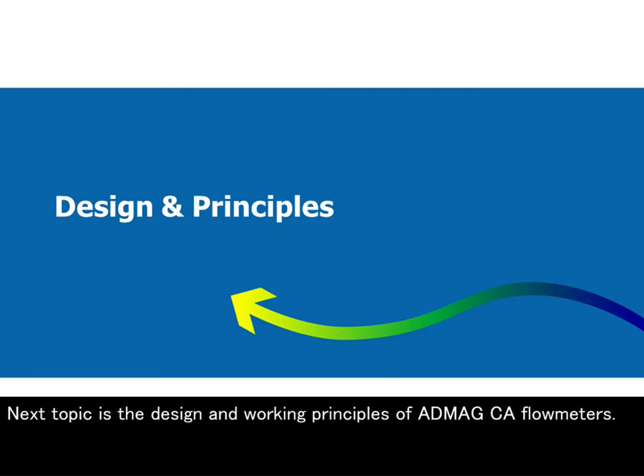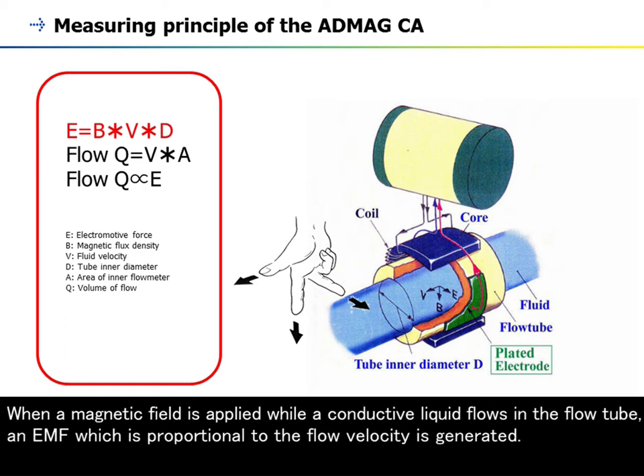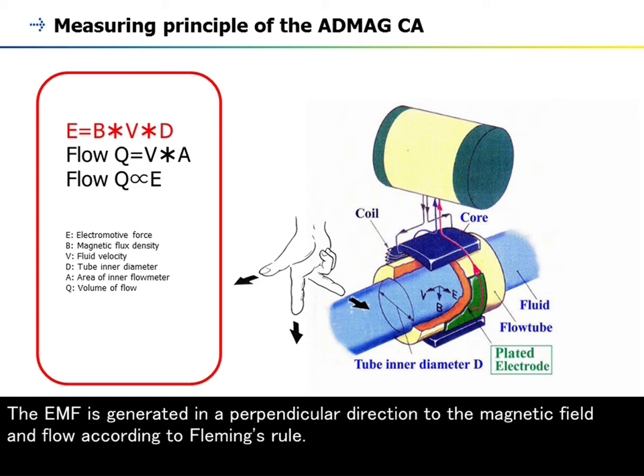The next topic is the design and working principles of ADMAG CA flow meters. The measuring principle of the ADMAG CA is based on Faraday's law of electromagnetic induction. When a magnetic field is applied while a conductive liquid flows in the flow tube, an EMF which is proportional to the flow velocity is generated. The EMF is generated in a perpendicular direction to the magnetic field and flow according to Fleming's rule.